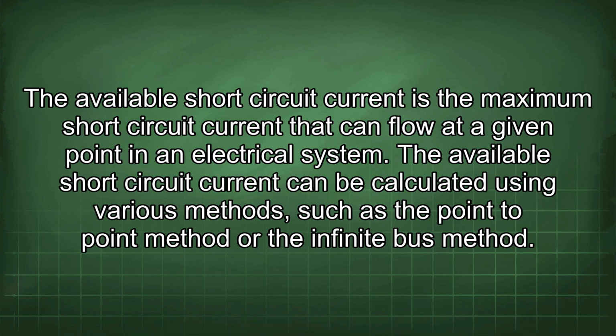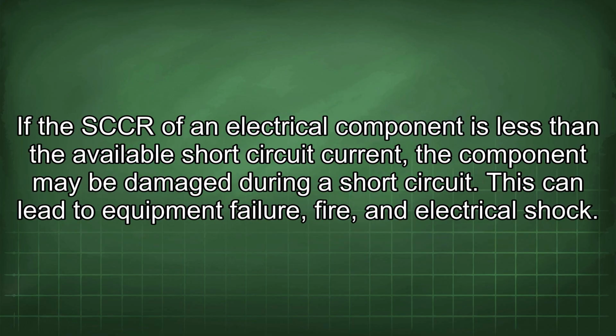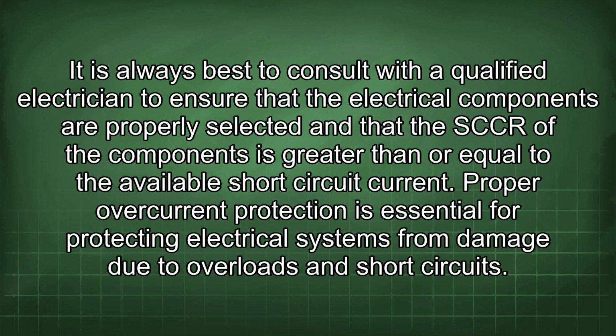The available short circuit current is the maximum short circuit current that can flow at a given point in an electrical system. The available short circuit current can be calculated using various methods, such as the point-to-point method or the infinite bus method. If the SCCR of an electrical component is less than the available short circuit current, the component may be damaged during a short circuit. This can lead to equipment failure, fire, and electrical shock. It is always best to consult with a qualified electrician to ensure that the electrical components are properly selected and that the SCCR of the components is greater than or equal to the available short circuit current.